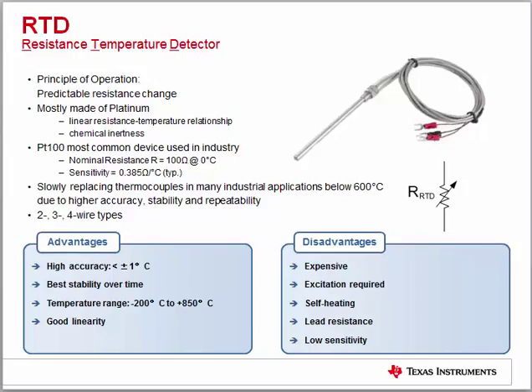Over the full temperature range, RTD resistance varies non-linearly from 35 ohms to 370 ohms. RTD downsides include cost — wire-wound types are much more expensive than thin film — and they require an excitation source. A 1°C change in temperature correlates to only a 0.385 ohm change in resistance, demanding accurate acquisition circuitry. Operation is simple: inject a current, measure the voltage, then calculate temperature using linear interpolation or lookup table values.